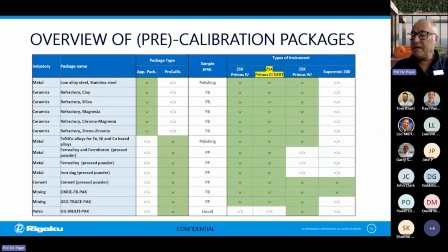We also have some pre-calibration packages, and for the spectrometer series ZSX Primus 4, Primus 4i, Primus 3 Next, and also for our Supermini 200, we have application packages available. Depending on your applications, you can have pre-calibrated packages, meaning the calibration is already installed in the laboratory in Japan where we produce the spectrometers. Or you can have calibration packages, where you get the standards and all the needed parameters for setting up the calibration. Then you just have to analyze the standards and calculate your calibration lines, and you have things up and working from the very first day you have the system installed.